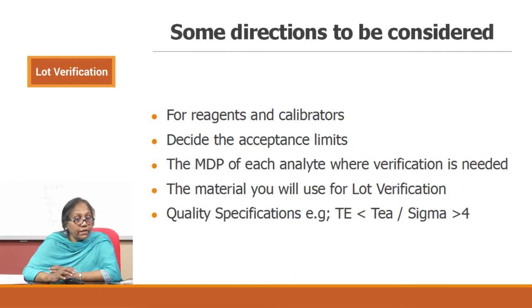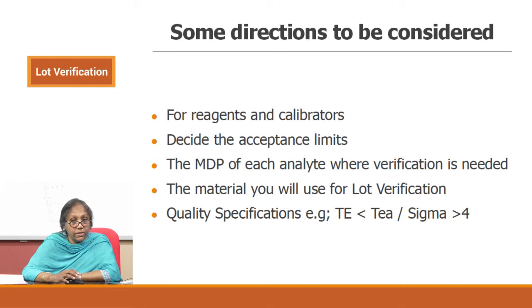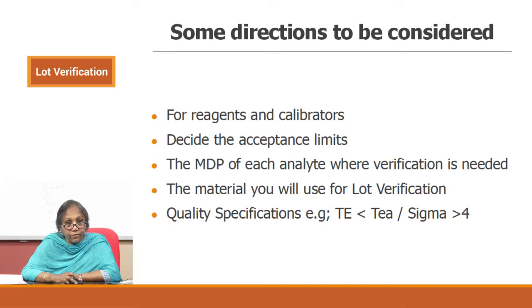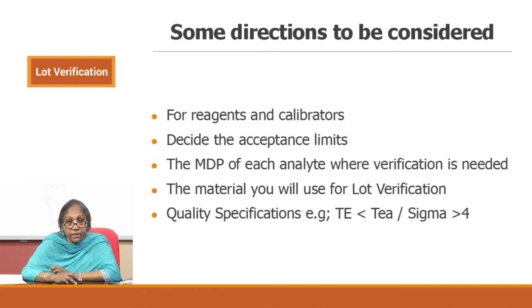Some directions to consider while writing your QSP: for quantitative tests, the acceptance testing may be defined for reagents as well as calibrators, and you have to decide on the acceptance limits. You also need to say whether the acceptance testing has to be done at all medical decision points or clinical decision points where verification is required.